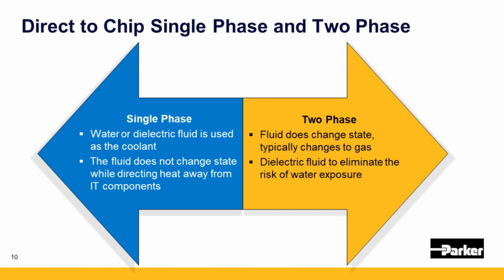A two-phase system is kind of the opposite - it's two phases of the same fluid, like refrigerant in your house or your car. As it goes across the IT gear, it picks up heat, taking advantage of that heat of evaporation, which takes a lot more energy than just changing a couple degrees of temperature in a single phase fluid. So the advantage is you're really taking advantage of that efficiency, but now you've got to manage two phases. You can't have gas come back into it because then you'll lose all your cooling. You have to make sure it gets from gas back to liquid, keep the pump going, and manage those two phases. So there's a bit of added complexity there.